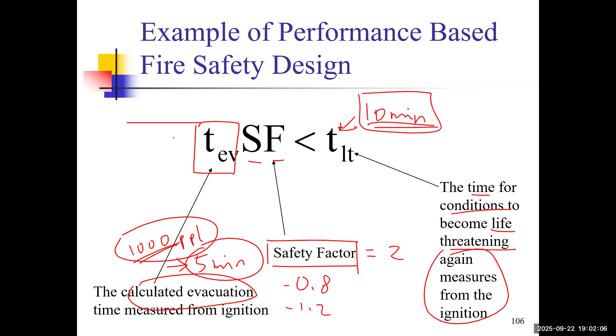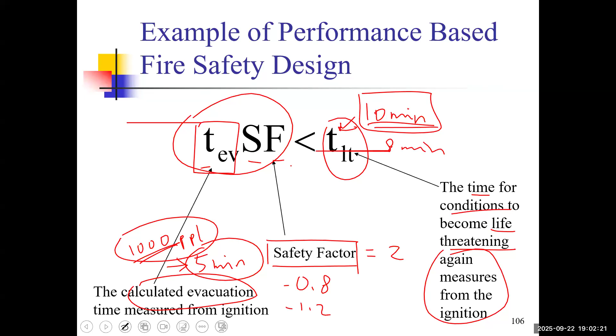So that is the time at which certain tenability limits are exceeded. As mentioned, if it is 10 minutes, we should make sure that the evacuation time and safety factor, the product of them, should be less than 10 minutes TLT. Of course, if it is 8 minutes, it should be lowered. The TEV and SF should be lowered.